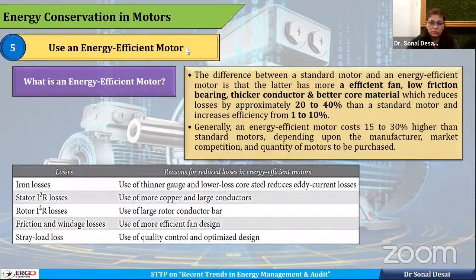Here the reason for loss reduction in energy efficient motors is given, that is why an energy efficient motor will have lower losses. Iron losses will be reduced because thinner gauge material is used. I square R losses will reduce because more copper is used. Just like that, rotor losses are reduced because a large conductor bar of copper is used. Friction and windage losses will be reduced because it will have an efficient fan, and stray loss will reduce because it will have a better quality and optimized design. So this will ultimately give a 1 to 10% rise in efficiency. And generally, energy efficient motors cost 15 to 30% more than standard motors, but a payback is achieved.